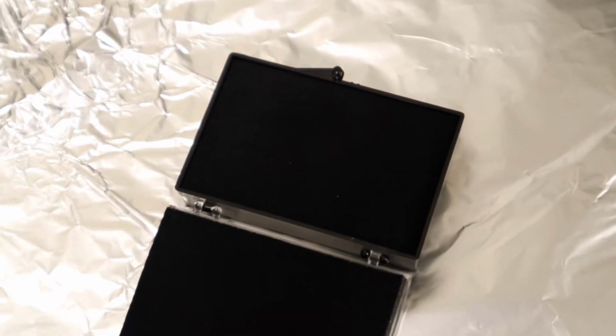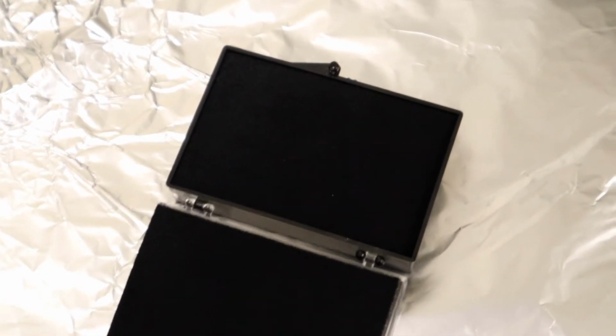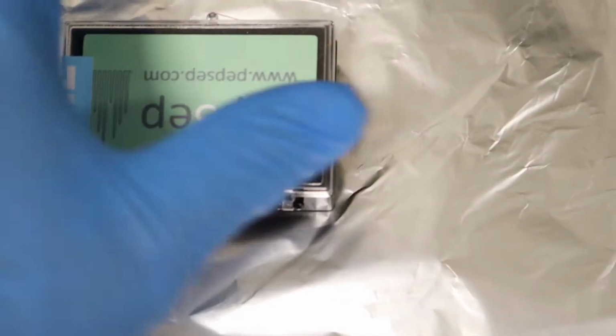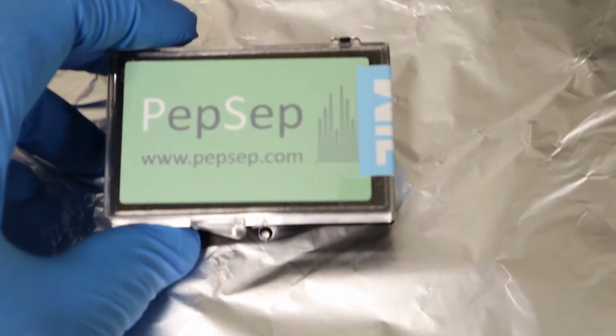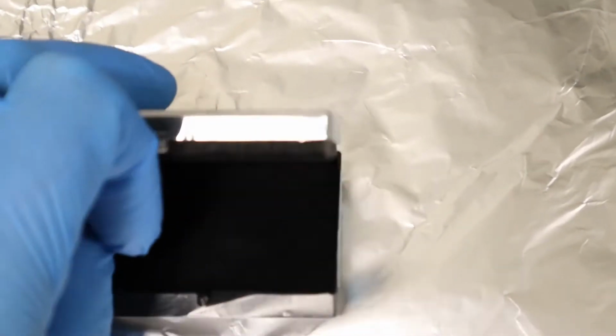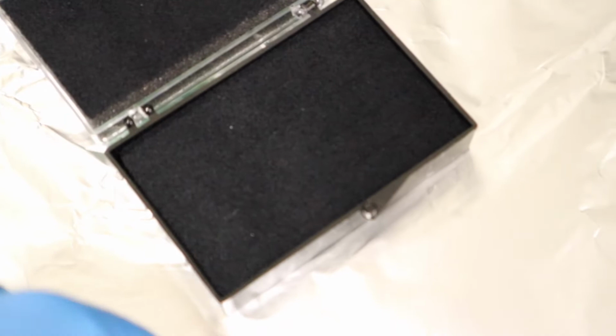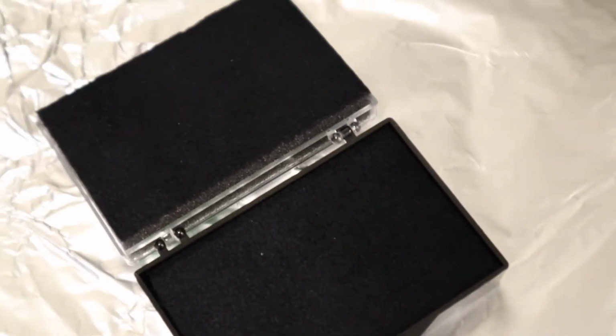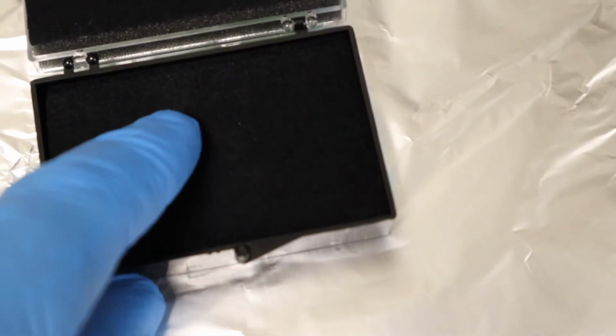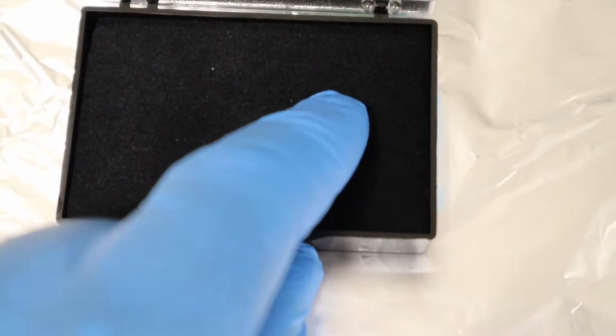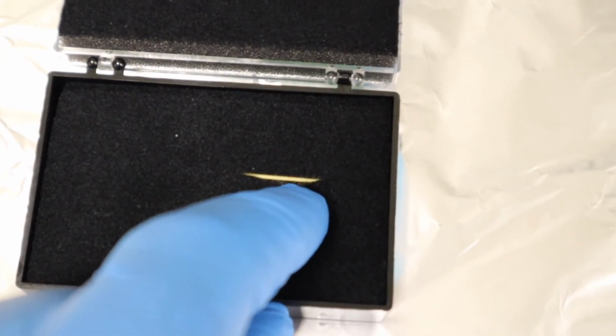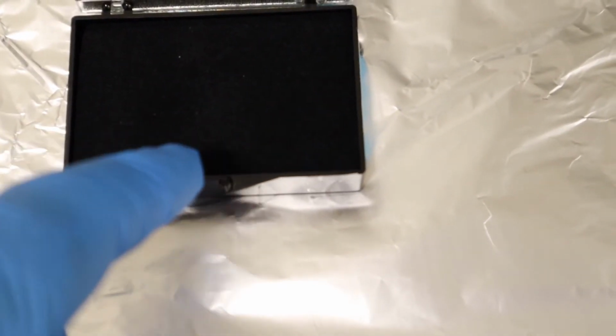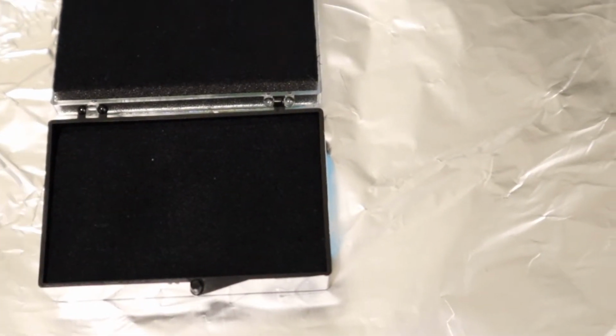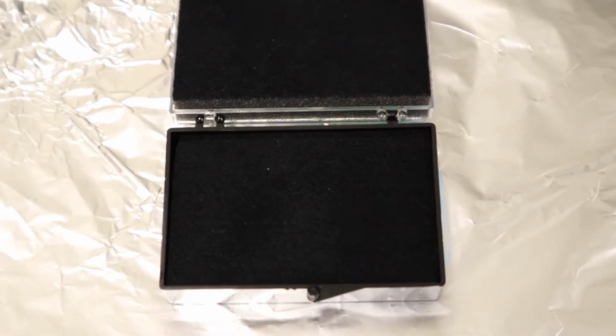Alright, so while the pumps are pumping down, I want to install an electrospray emitter. Now the ones that I'm using are these from PepSep, and they come embedded in this foam case, so they look like there's none in here, but if you look closely you'll see some. If you peel back the foam, you'll see a little yellow sleeve. Now that yellow sleeve is over the sharp end of the emitter, and it's just to keep it safe in transit. We're going to remove that, and we're going to put our own yellow sleeve on it so that it fits into the electrospray T.